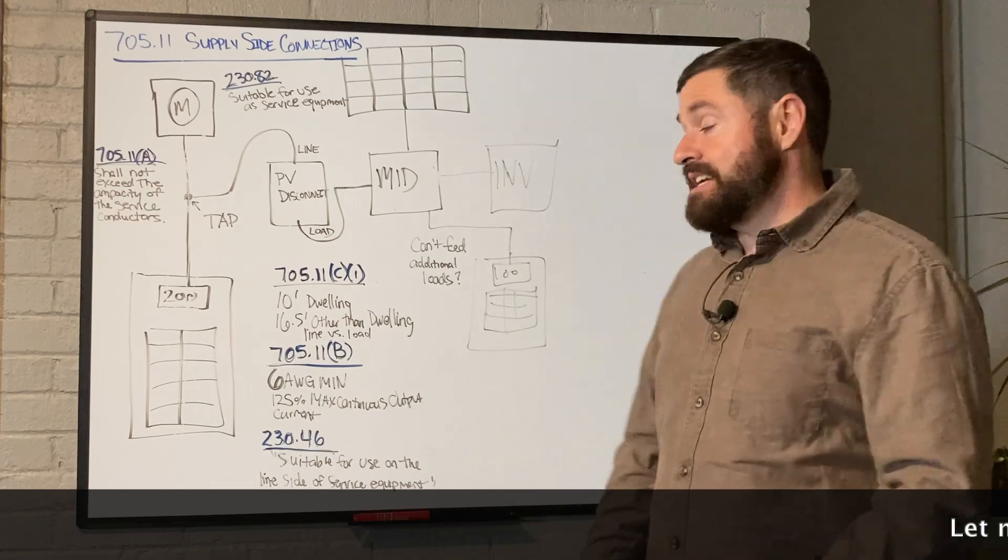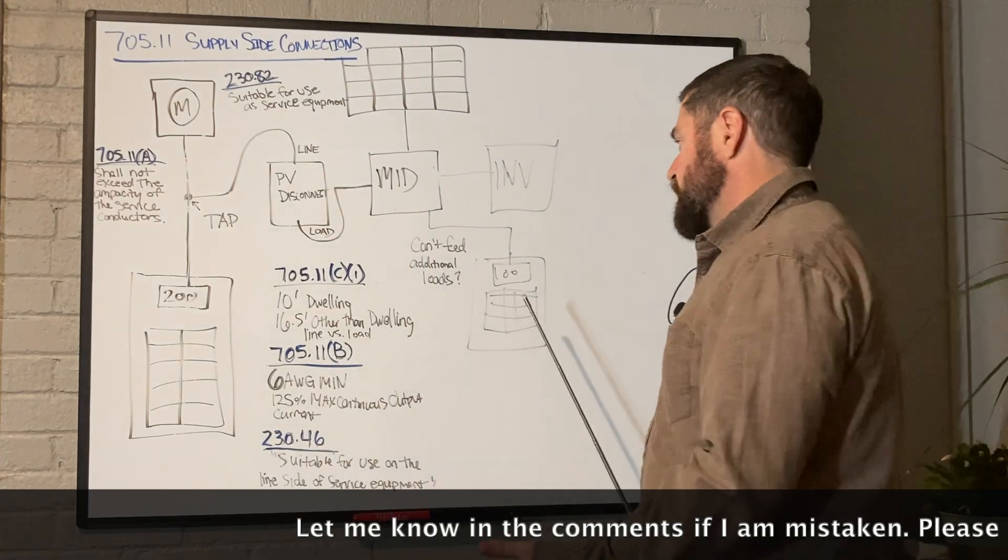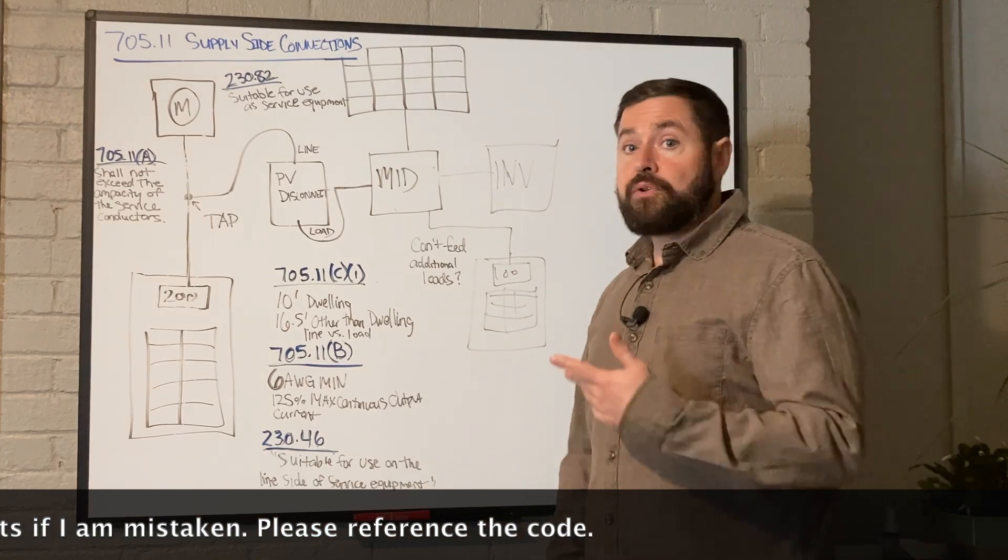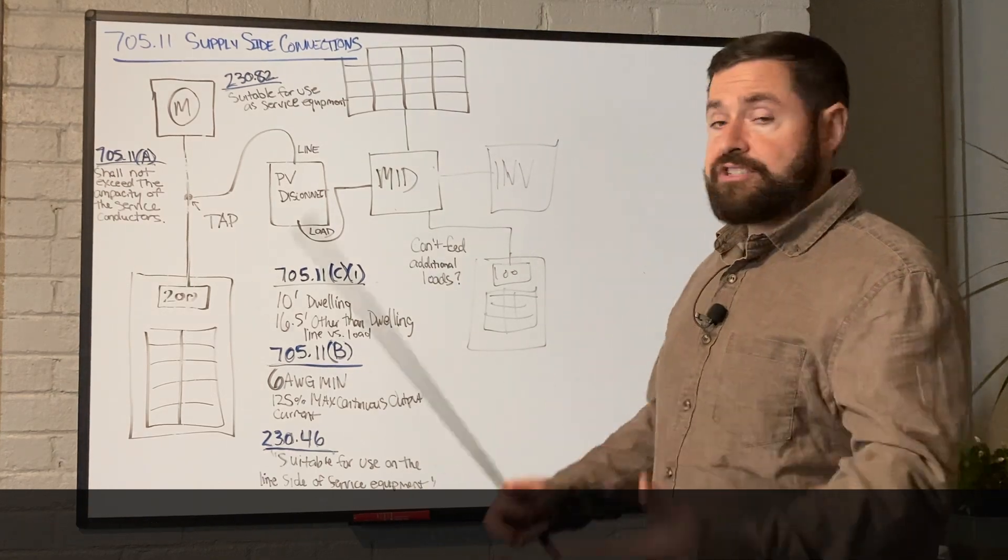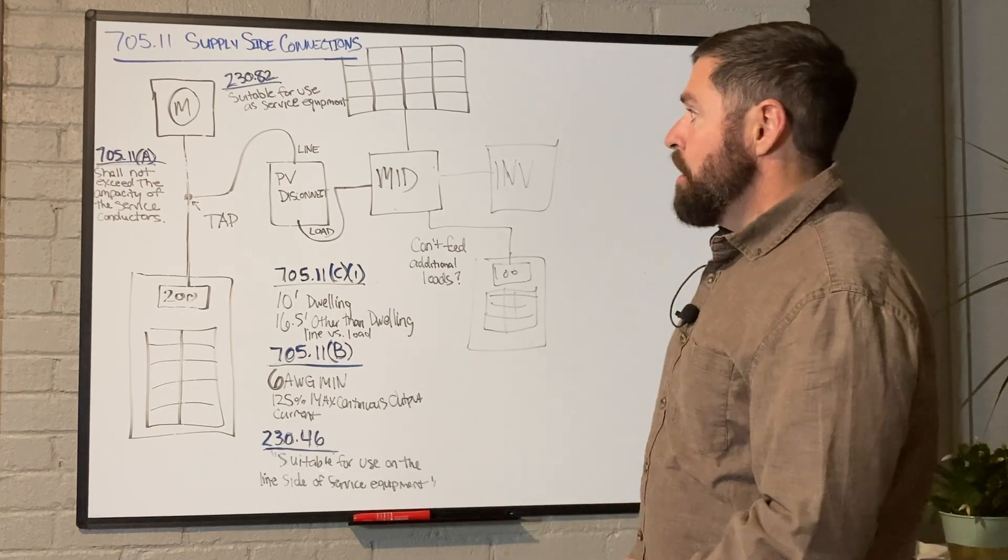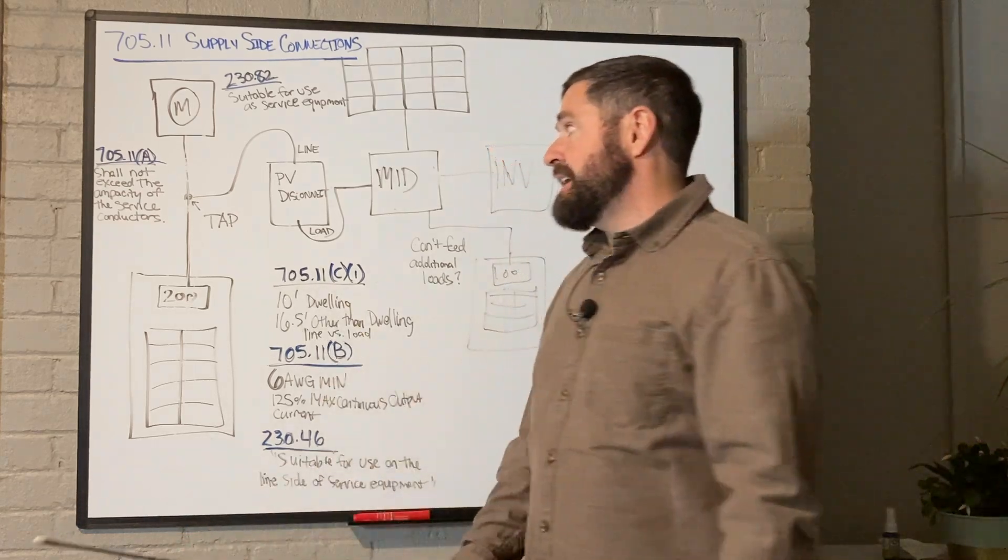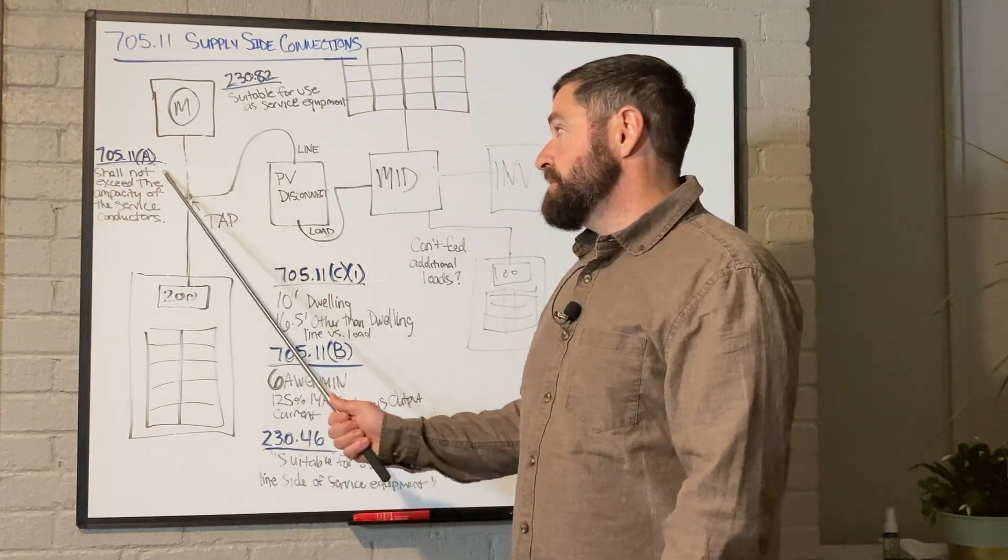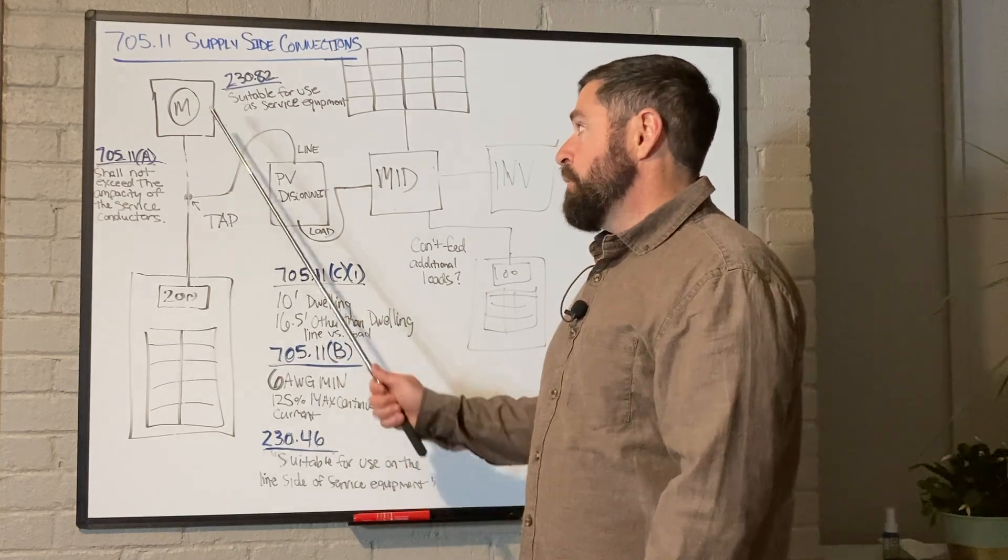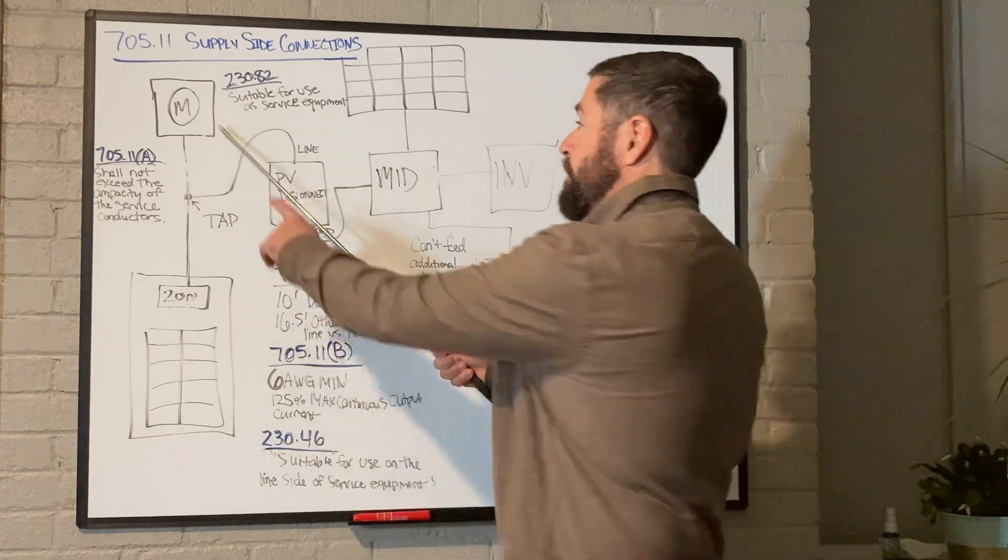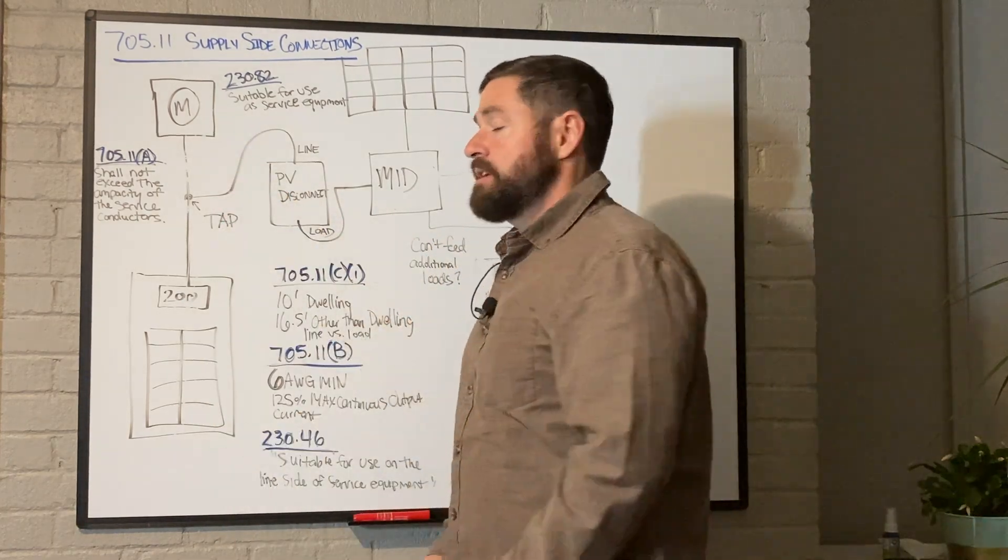Now, there's nowhere in the code that I've been able to find that specifically states you are not allowed to do this, but there are going to be some people in the industry that are going to say you can't actually line side tap an energy storage system that feeds downstream loads. If you ever get into that situation and you need to remediate it, one easy fix is just to add a service disconnecting means upstream of the tap that will then trip that breaker if you ever tried to pull more than 200 amps through the service, and that would essentially turn this from a line side tap to a load side tap.